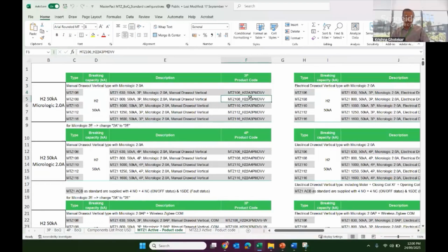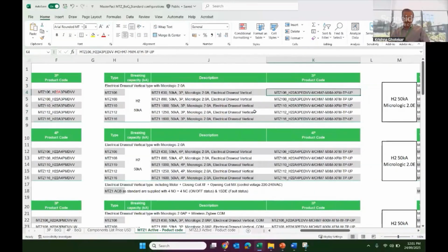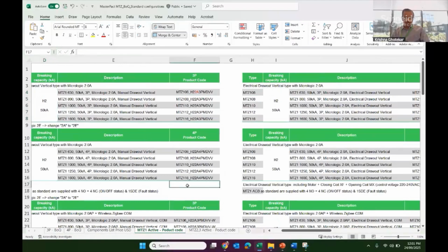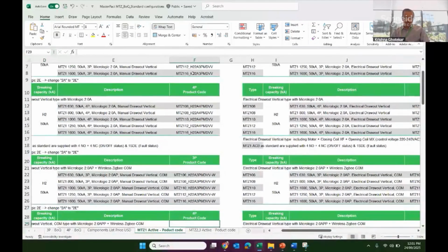So in case of 2A, if you need 2E, you can just change from the 2A type of breaker to 2E type. That way it's much more flexible. If you want H1 type breaker instead of H2, as per that you can derive the part numbers. Of course, if you need communication connectivity, then for AP or EP, whatever the type of trip unit, you just add -W to the end and it becomes a wireless type.